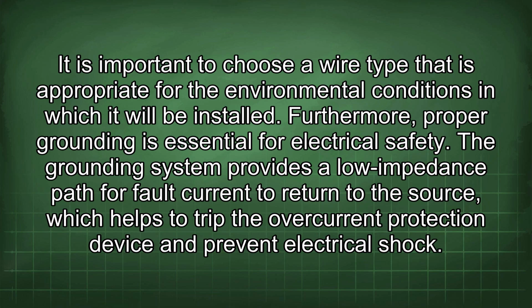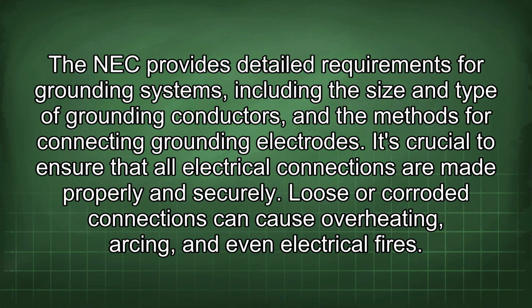Furthermore, proper grounding is essential for electrical safety. The grounding system provides a low impedance path for fault current to return to the source, which helps to trip the overcurrent protection device and prevent electrical shock. The NEC provides detailed requirements for grounding systems, including the size and type of grounding conductors and the methods for connecting grounding electrodes.